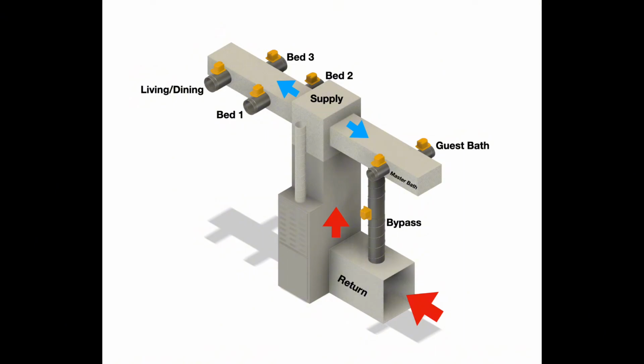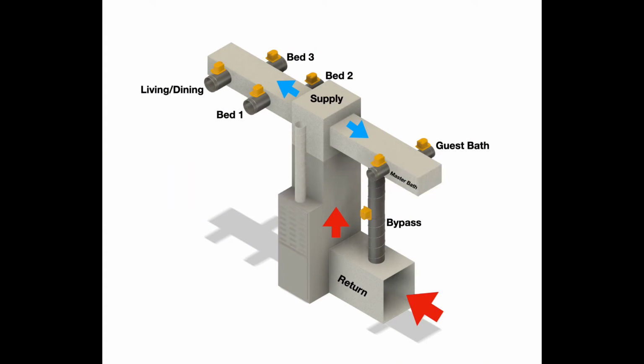So in the event there's too many dampers that are closed, that return damper or bypass damper will open and allow air to circulate back through the air handler, back into the ductwork, so we don't overpressurize the ductwork or cause the blower motor to work too hard and overheat, or cause the heat exchanger to overheat and fail prematurely. Or in cooling mode, we don't want to cause that cooling coil to freeze up or ice up. So you may or may not need a bypass damper. Every situation is unique and different and should be designed according to the building, size of the system, how many supply registers you have, type of system, etc.